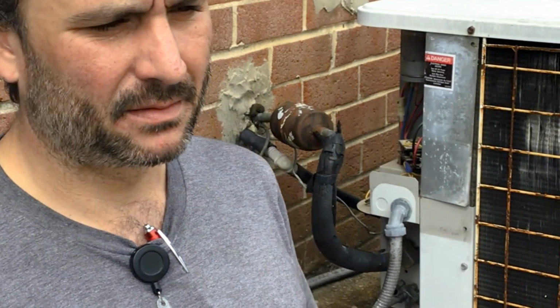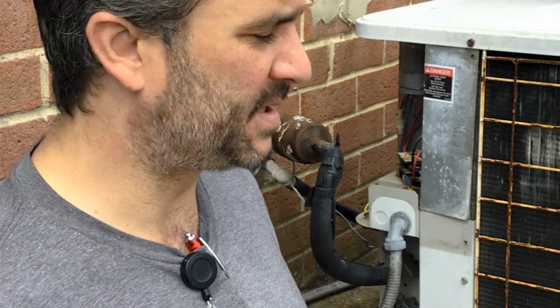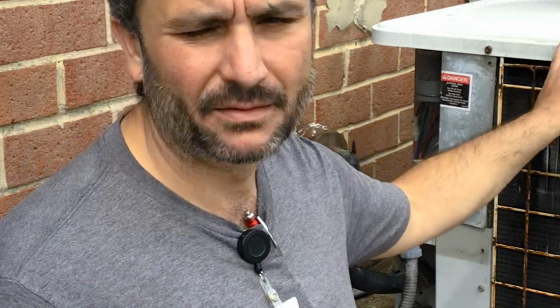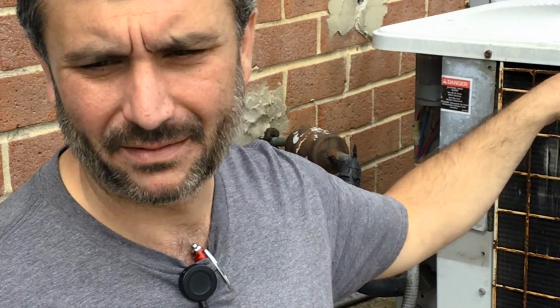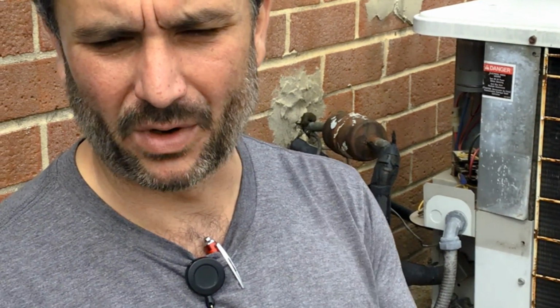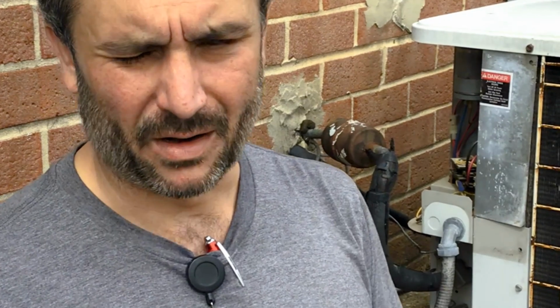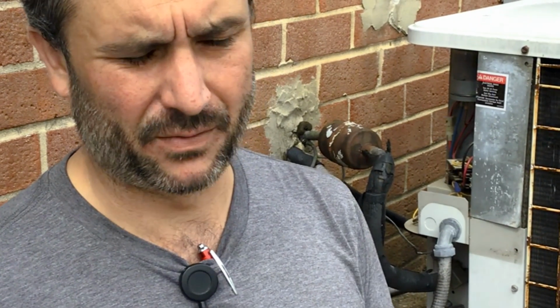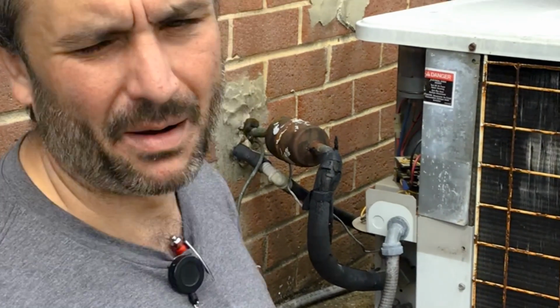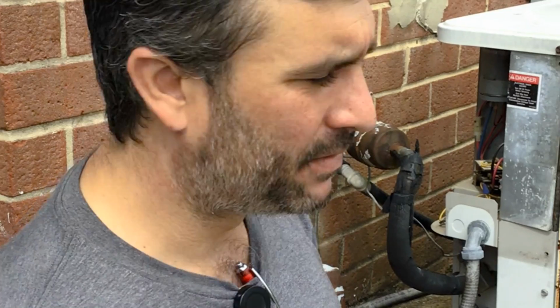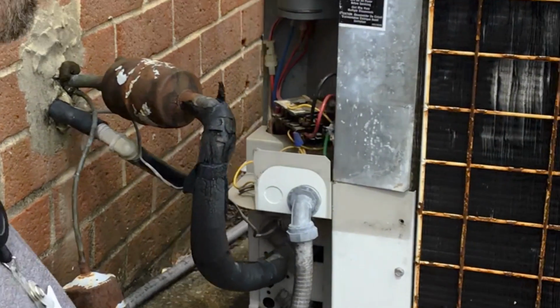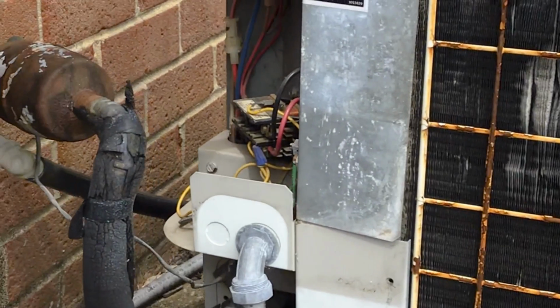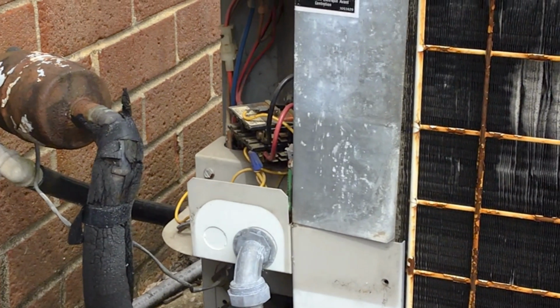The best way to narrow things down when you're troubleshooting one of these systems is to know that they rely on three different types of voltage to operate: a 24 volt circuit, a 120 volt circuit, and a 240 volt circuit. So you save yourself a lot of time determining in which phase you're having your problem, and a lot of times it can be determined by just a visual inspection. For a quick example, I have the breaker off to this unit, so we have no 240 volts going to it.